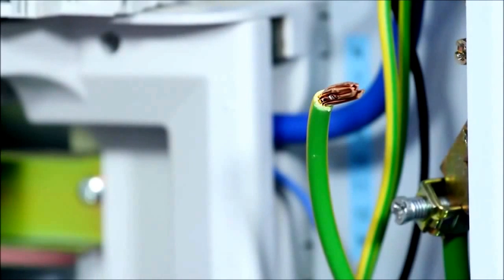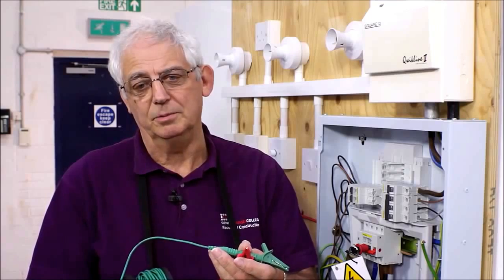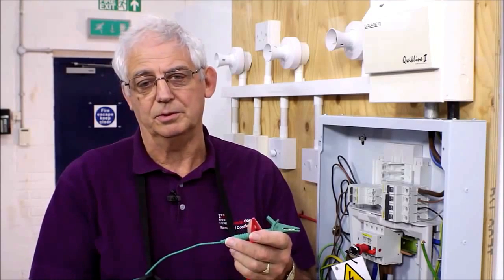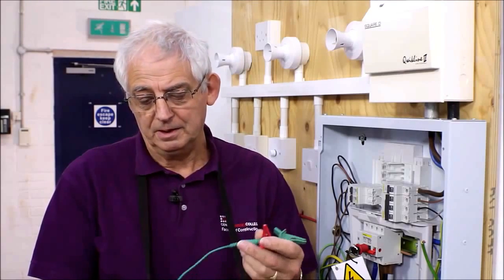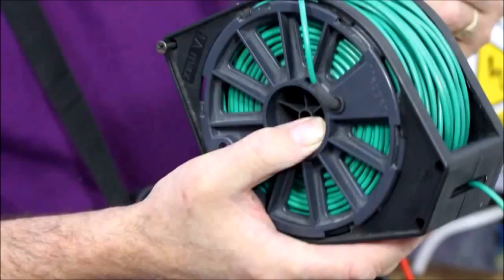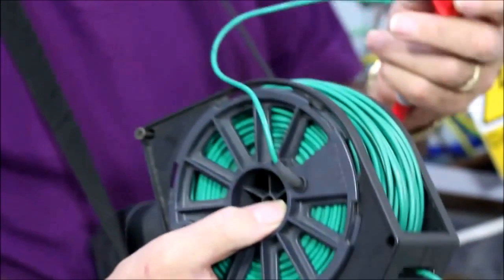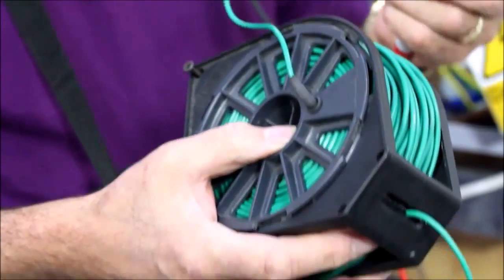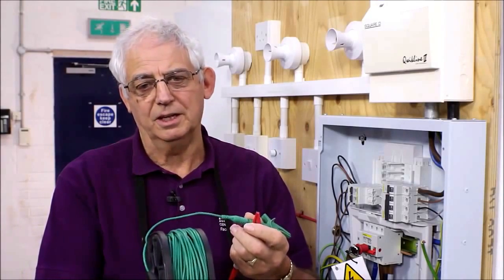Because this bonding conductor could be quite a long conductor, it's going to be what we call a long lead test. To carry out a long lead test, obviously I need a long lead, or I can use a long piece of cable, but it is much better to use the right type of equipment if you possibly can. The problem with this long lead, of course, is that it's going to have a resistance of its own. So for this test, I need to zero the leads, taking into account the resistance of this lead, okay?